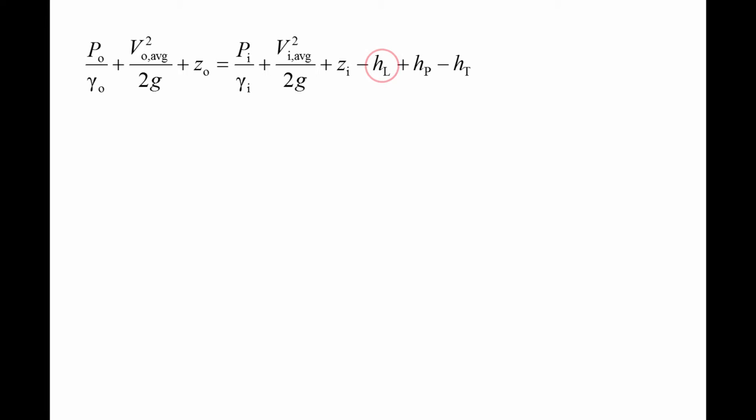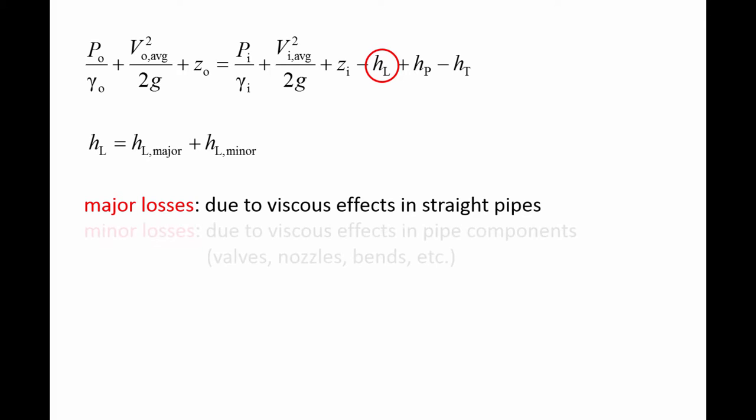Let's take a closer look at the head loss term HL. For convenience, the head loss is broken into two parts: the major losses, denoted by HL major, and the minor losses, denoted by HL minor. The major losses are related to viscous effects in straight pipes only. The minor losses are related to viscous effects in pipe components, such as valves, nozzles, bends, and so on.